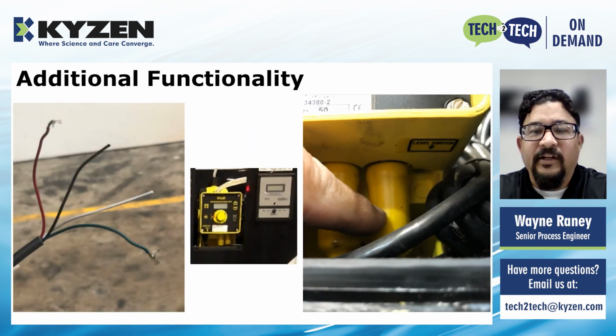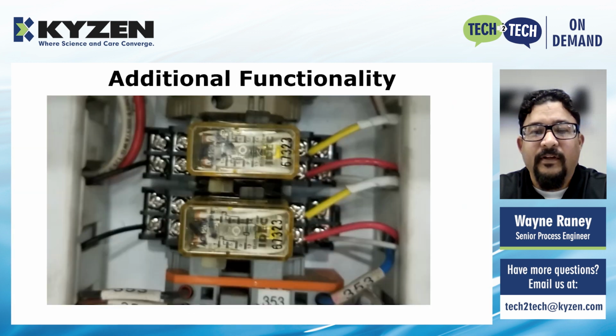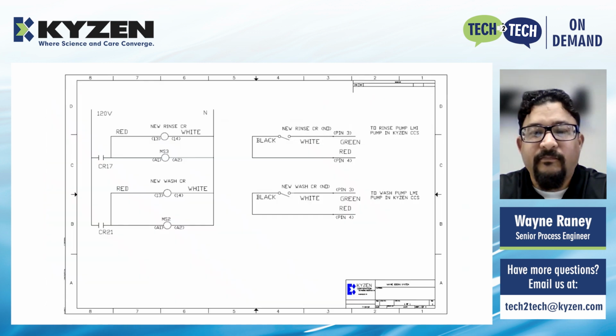Another function we added to help this customer was a cable to the system, which will make the CCS on both the wash tank and rinse tank go into idle mode when the respective pump is off. This will ensure that the system is not adding chemistry when the washer is shut down. This was another one of the theories to the high chemistry usage. The system idle feature required adding a couple relays, one for the wash pump and one for the rinse pump. And we also drew up schematics for the customer's records.